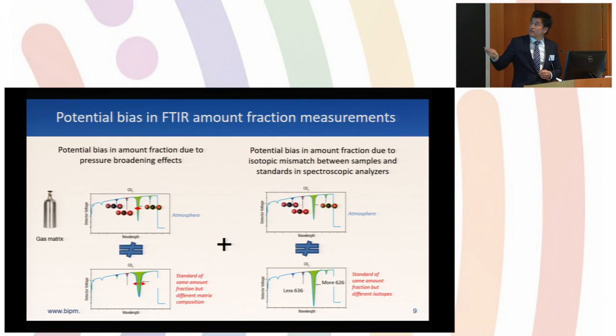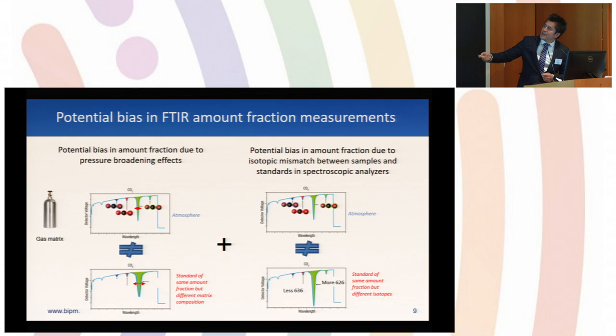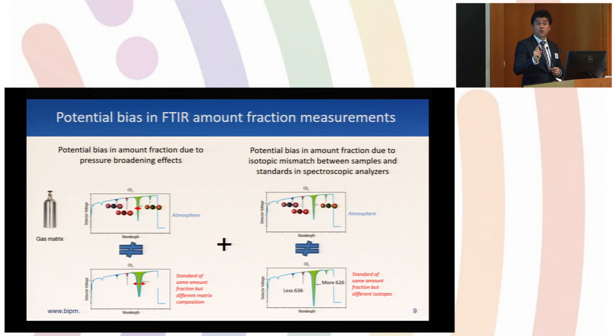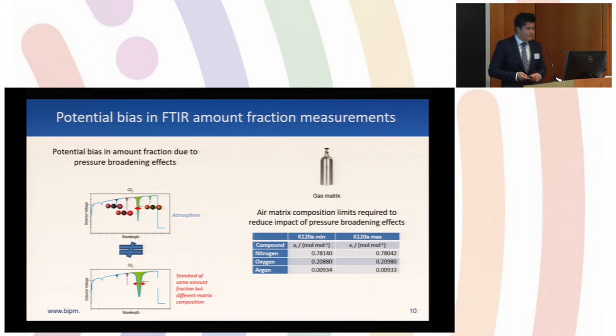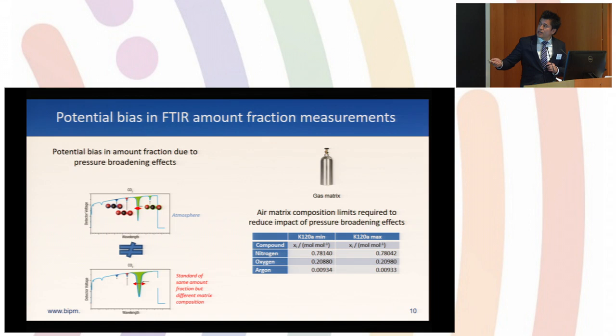The second effect is the potential bias due to the isotopic mismatch between the reference standard and the sample. If in your reference you have more 626 than 636, you will have an automatic bias, because some optical systems are only measuring the main isotopologue and are not correcting for both. What we have done during K120 to avoid pressure broadening effects is we asked participants to provide very controlled gas matrix composition — minimum and maximum amounts of nitrogen, oxygen, and argon — to reduce the potential bias from differences in gas matrices.